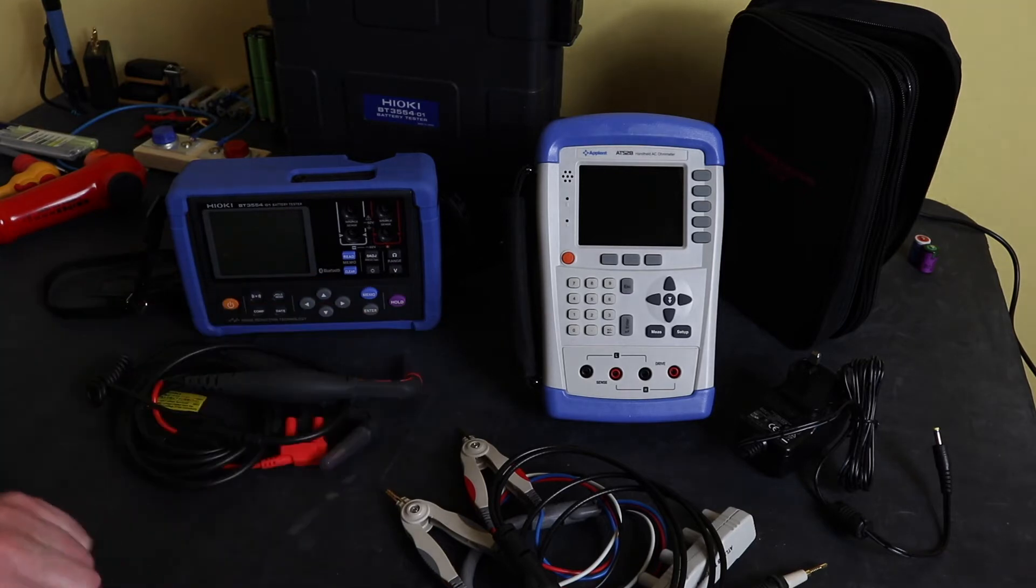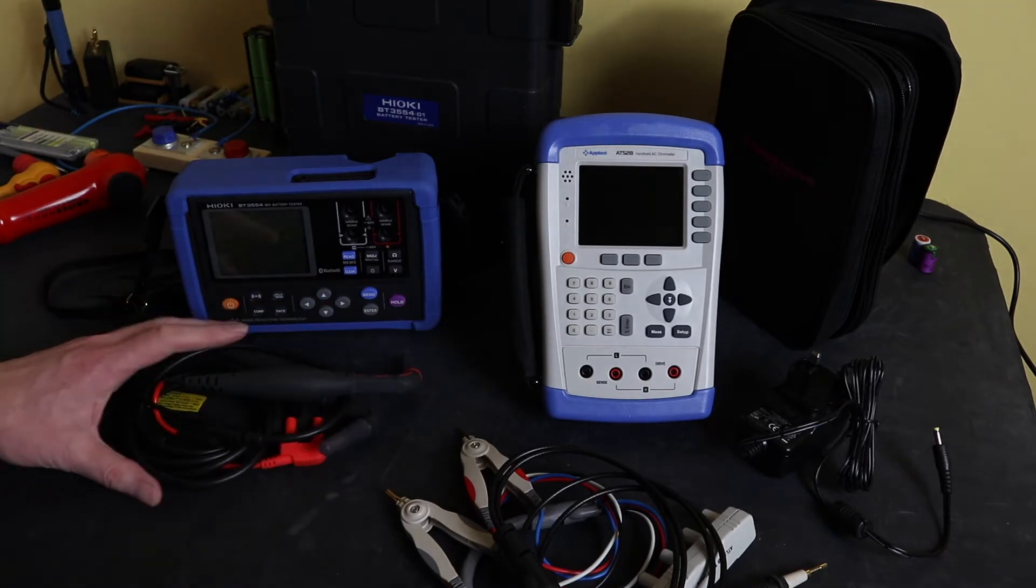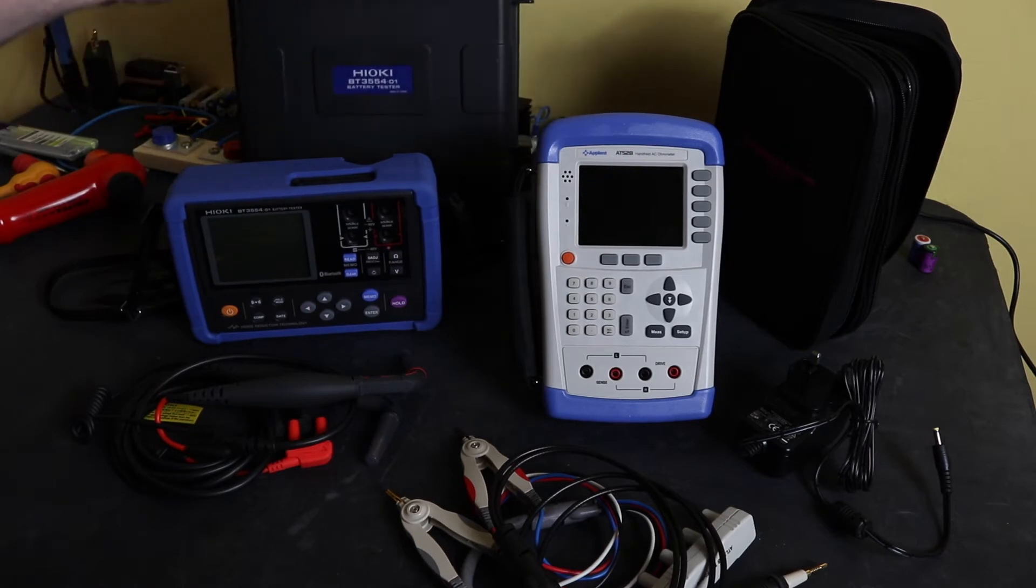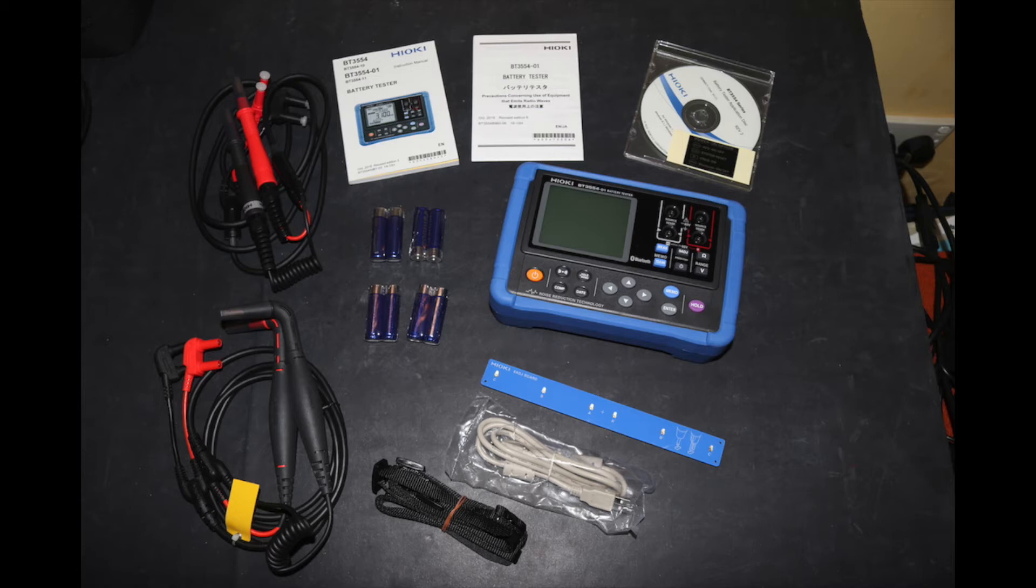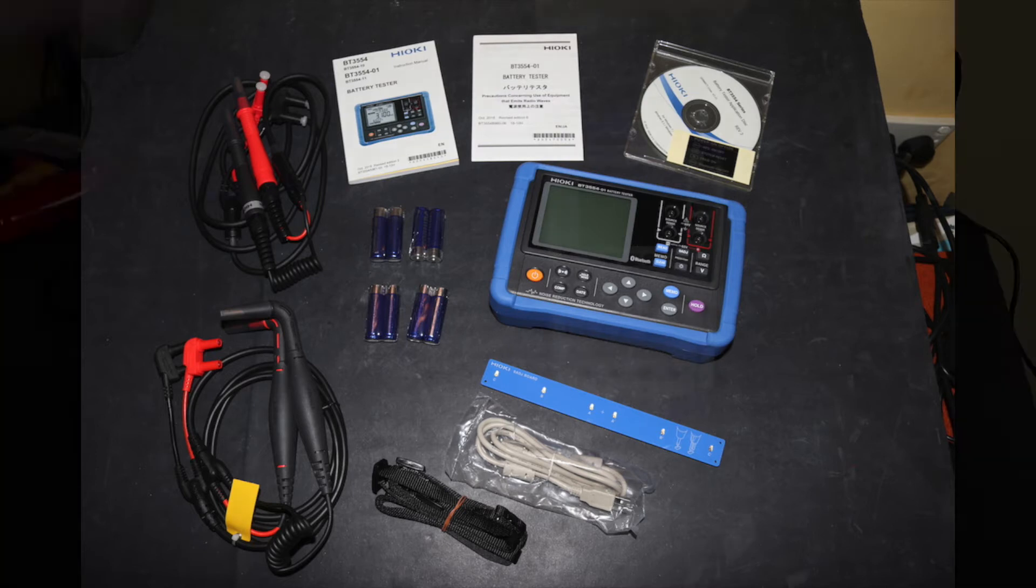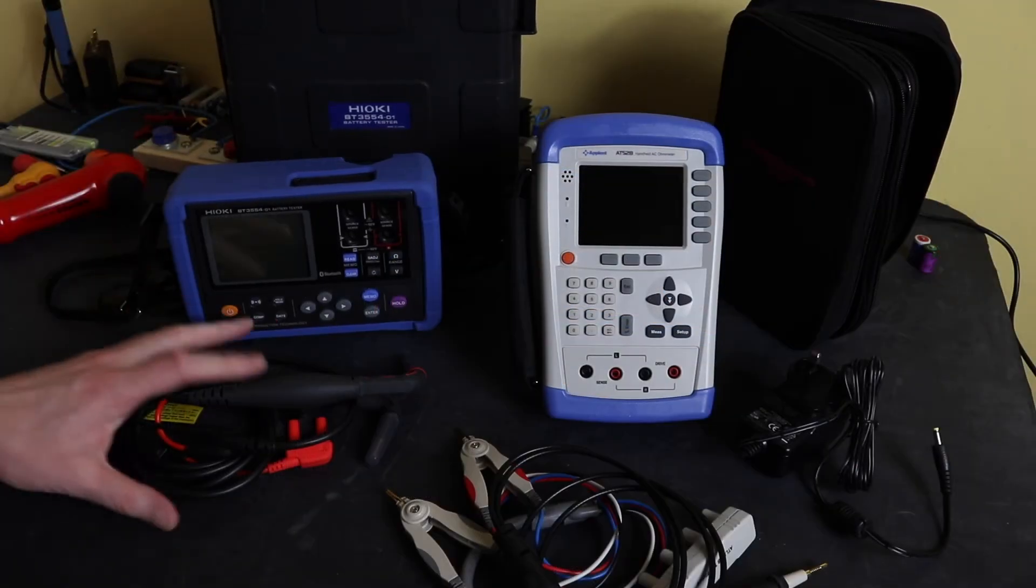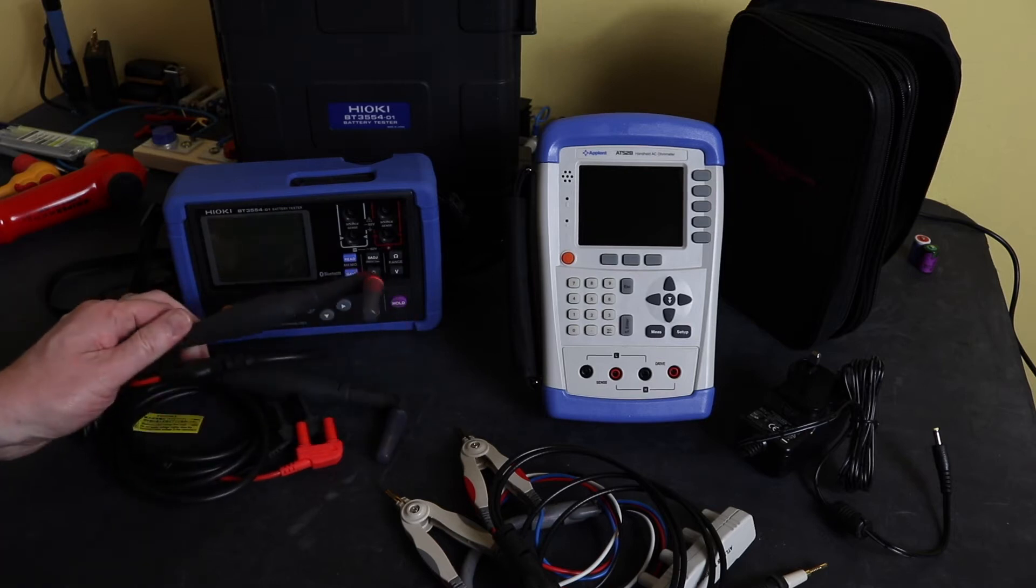The Hioki comes in a hard case. You also get a zero ohms adjust board in there and one set of probes and the USB comms lead. This also has enough space for a second set of leads, which is the right angled probe tips that I've got here, but you have to buy them as extras.